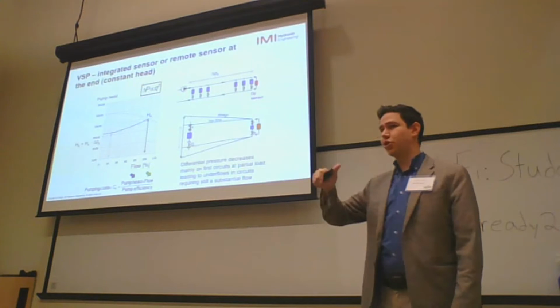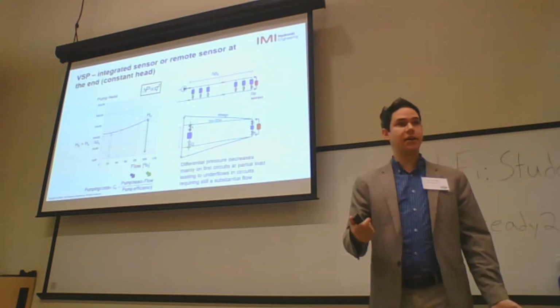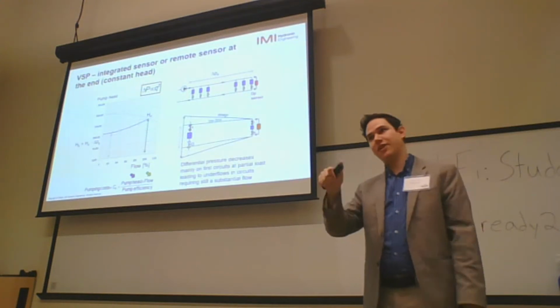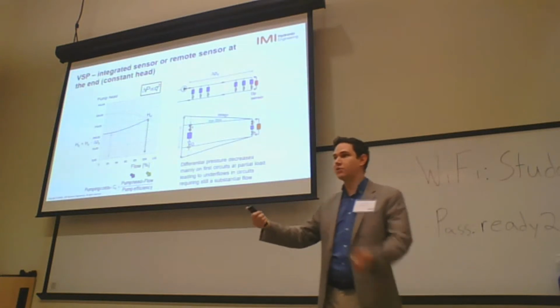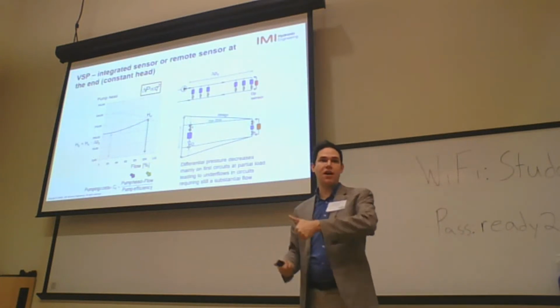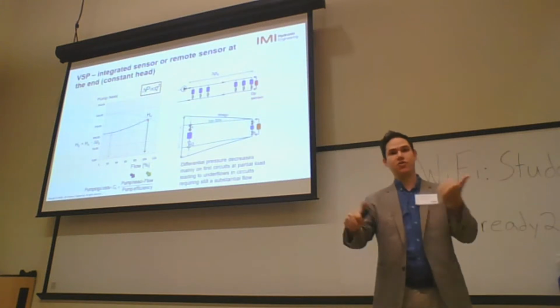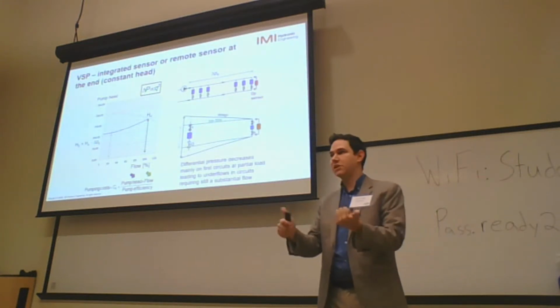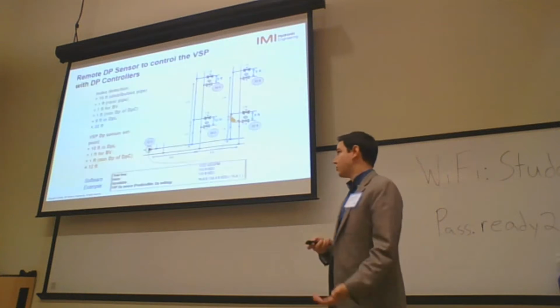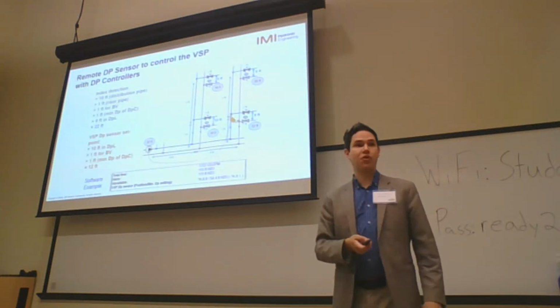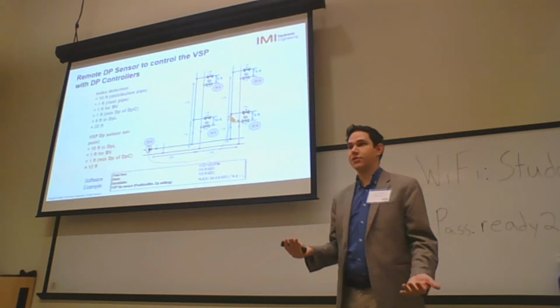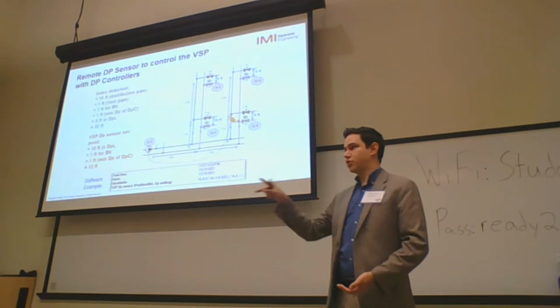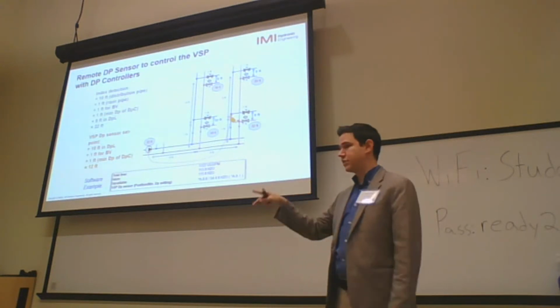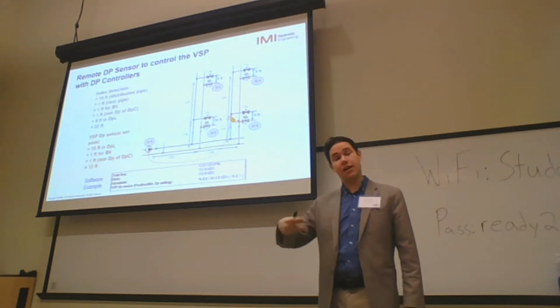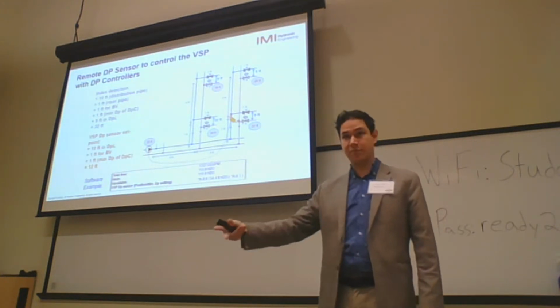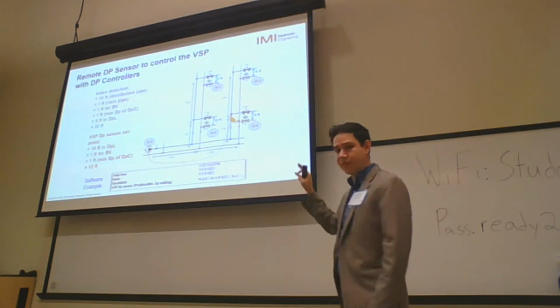So when you're thinking about the 2/3 rule of thumb, it is a way to be safe and always get enough water for everybody, and also a way to save some energy. So you're getting a mid-term between the two. The best way to do it is always through the right calculation. Nowadays, there is software that can calculate the pressure drop set point that you need on the DP sensor, and the best location for the DP sensor on the installation.